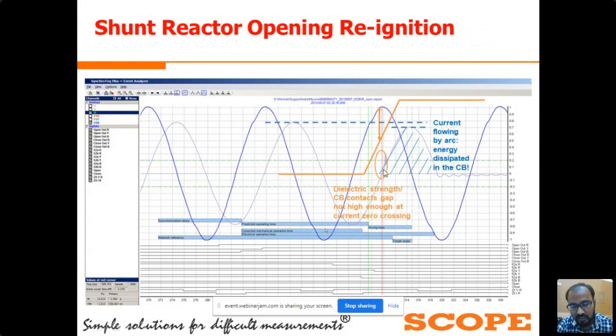So the current is again reignited between the CB contacts up to the next half cycle. You can see this portion. This phenomenon we call the reignition of current. From this point to this point, that is near to half cycle, the arcing current continuously flows between the CB contacts. Once again the arcing current goes to natural zero.